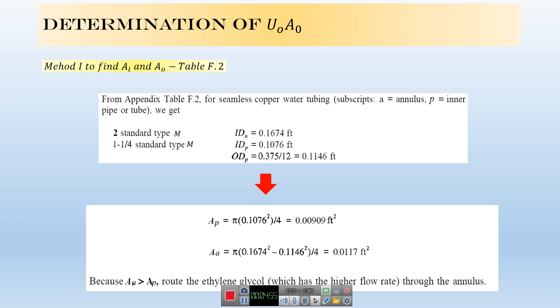The first step to design any heat exchanger is determination of thermophysical properties. The second step is to find diameters and flow areas. You can use two methods: Method 1 uses Table F2, which gives standard sizes for the annulus and pipe — IDA, IDP, and ODP. From those, you can calculate the flow areas for pipe and annulus.